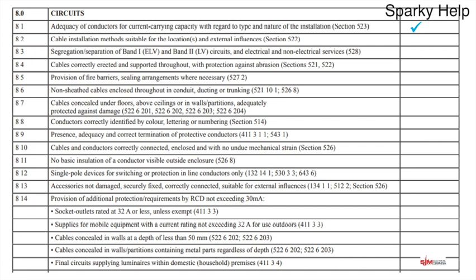Regarding external influences, it comes back to IP ratings. If it's a really dusty environment, has all the equipment been installed suitable for dusty environments? Or if it's a wet location or whatever it happens to be — whatever's been installed, is it suitable for it? Make the decision; hopefully it will be a yes.